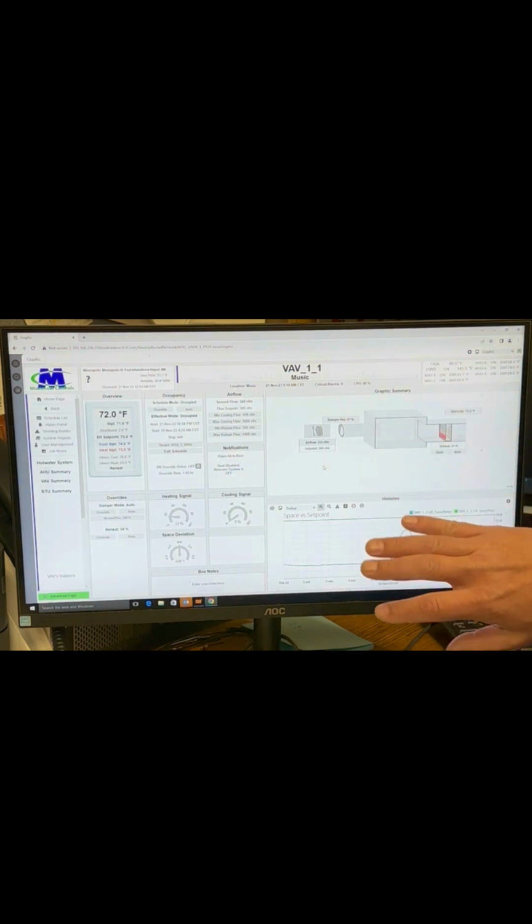Maybe. So, I think this is a huge advantage. And I think getting things broken off that don't need to be run. I mean, like RTU3, childcare, that's running from 6 a.m. to 9 p.m., 7 days a week. No. That can be shut down at 4 o'clock in the afternoon.